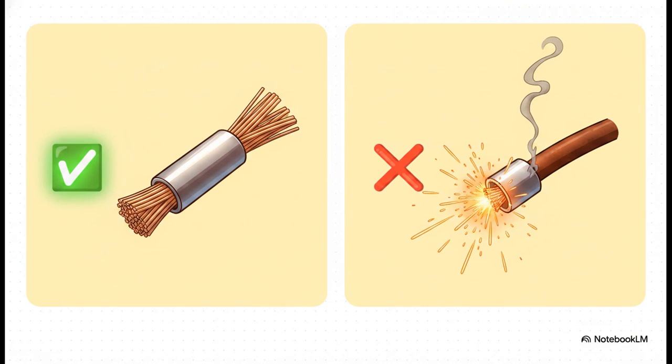I need to call out a major Red Seal trap right now from Rule 12-116. Pay close attention. If you're using fine strand conductors, you must use connectors identified for them or standard connectors with a ferrule. But, and this is a huge but, if you have a solid conductor, a ferrule shall not be used. I repeat, never, ever put a ferrule on a solid conductor. It is strictly prohibited by the code because it just won't grip properly and it will absolutely fail under a load.